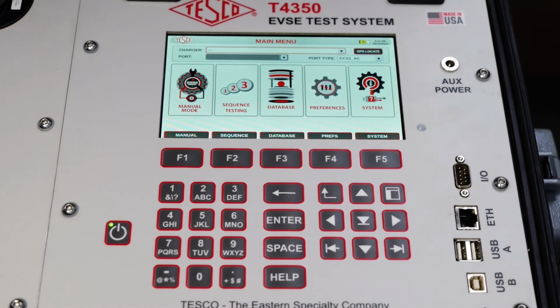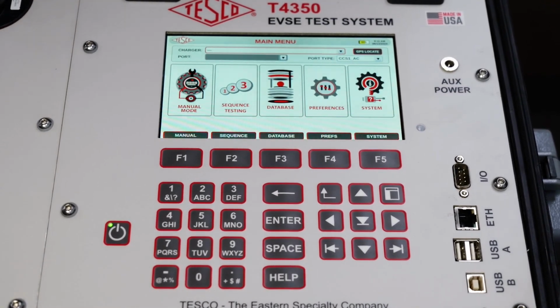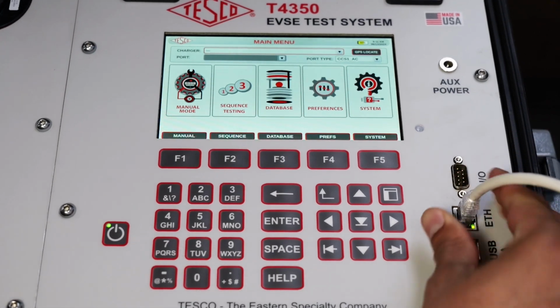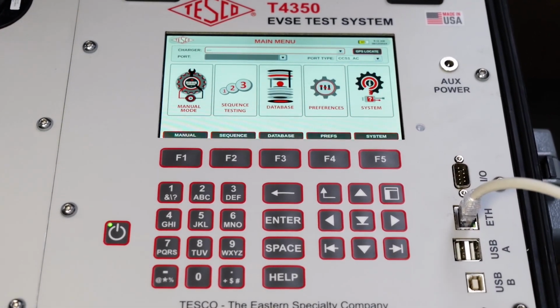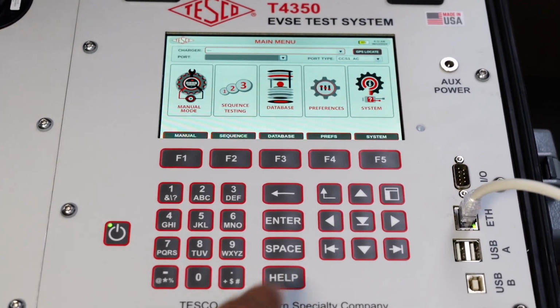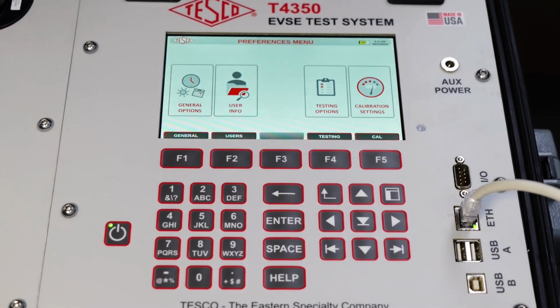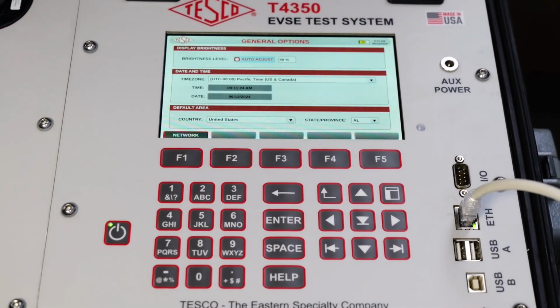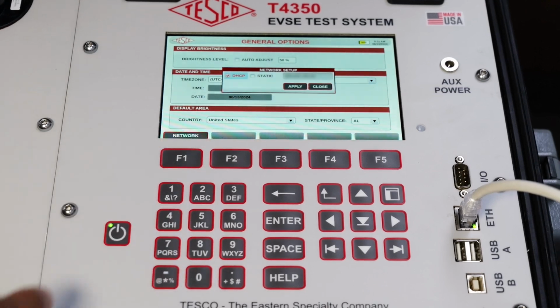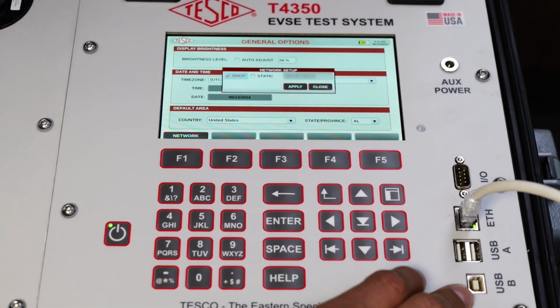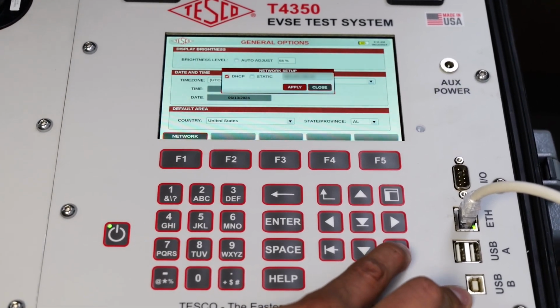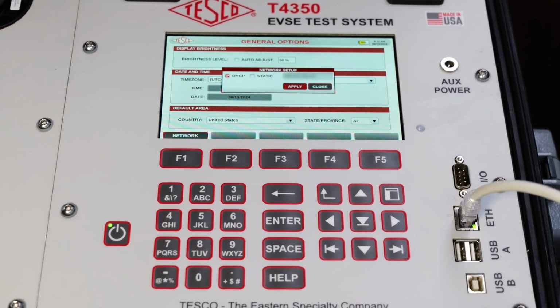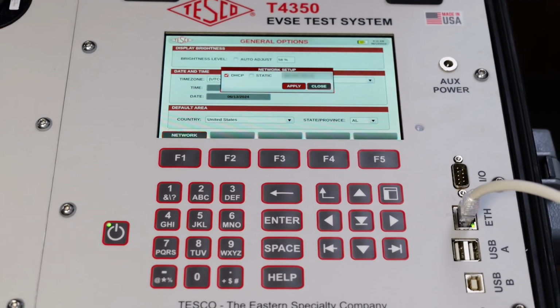Now we're going to go into downloading the test reports. First I'm going to connect an Ethernet cable onto this port here. Then I'm going to go into the preferences button, then the general button, and from there the network button. From here you could plug in your IP address, and once you get that configured, we're going to hit apply, and switch over to the computer at this point.